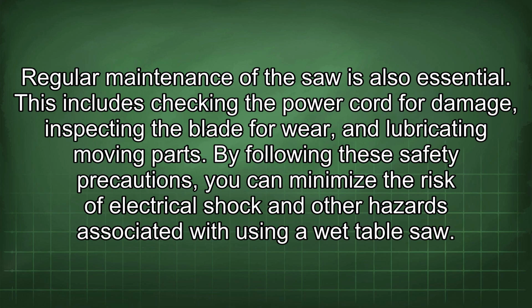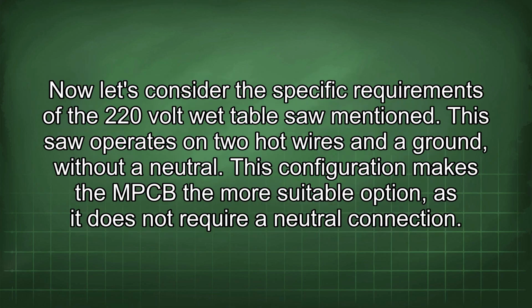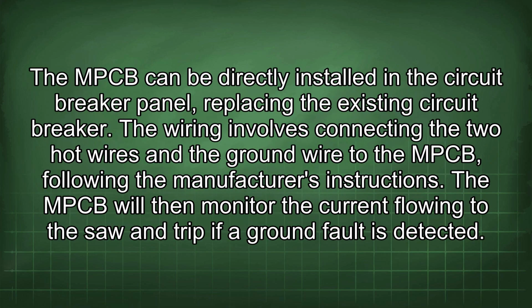Now let's consider the specific requirements of the 220-volt wet table saw mentioned. This saw operates on 2 hot wires and a ground, without a neutral. This configuration makes the MPCB the more suitable option as it does not require a neutral connection. The MPCB can be directly installed in the circuit breaker panel, replacing the existing circuit breaker.